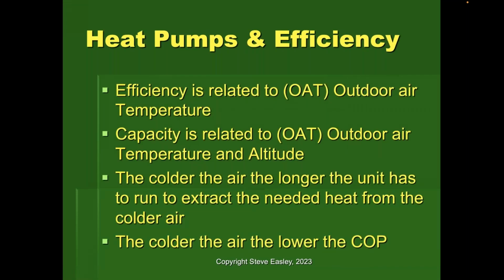All right, so let's review this quickly because I know I'm covering a lot of material quickly. Efficiency of a system is related to the outdoor air temperature. In other words, as the outdoor air temperature drops, because the heat pump is basically trying to extract heat out of the air, it makes common sense that if the air is colder, that unit has to work harder and longer to extract that heat out of the air. The capacity, in terms of the ability to heat your whole entire home, is also based on outdoor air temperature and to some degree altitude because of the density of the air. The colder the air is, the longer the unit has to run to extract that heat from the air. So the colder the air, basically the lower the COP for traditional equipment.